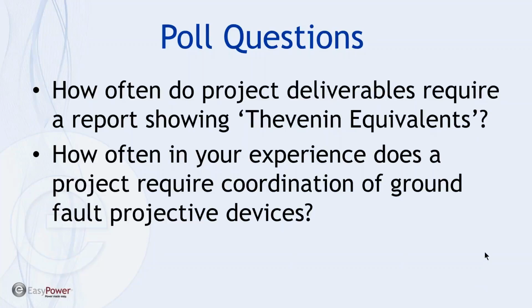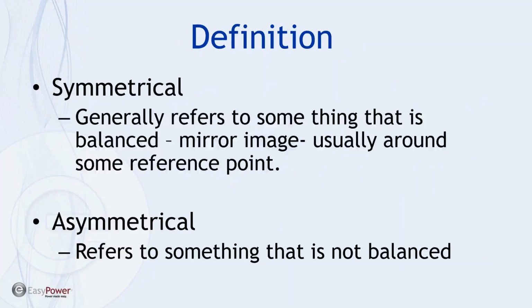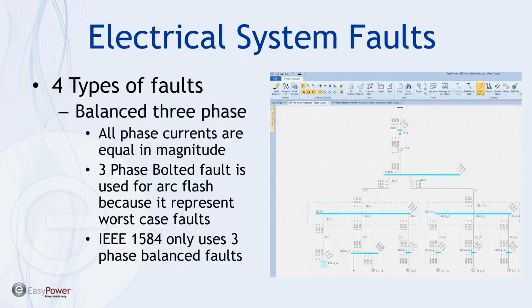So let's mosey. As I mentioned earlier, in general, they're fairly simple definitions. Symmetric refers to something that's usually balanced, or in many cases a mirror image in terms of the waveform, and the balance is usually around some reference point, and usually in waveform parlance that's the zero axis in the amplitude. Asymmetrical then by default is anything that's not balanced. Now, the reason that I think, or at least in my opinion, there's some potential room for confusion is that these terms are applied in different areas, not just in the fault current.